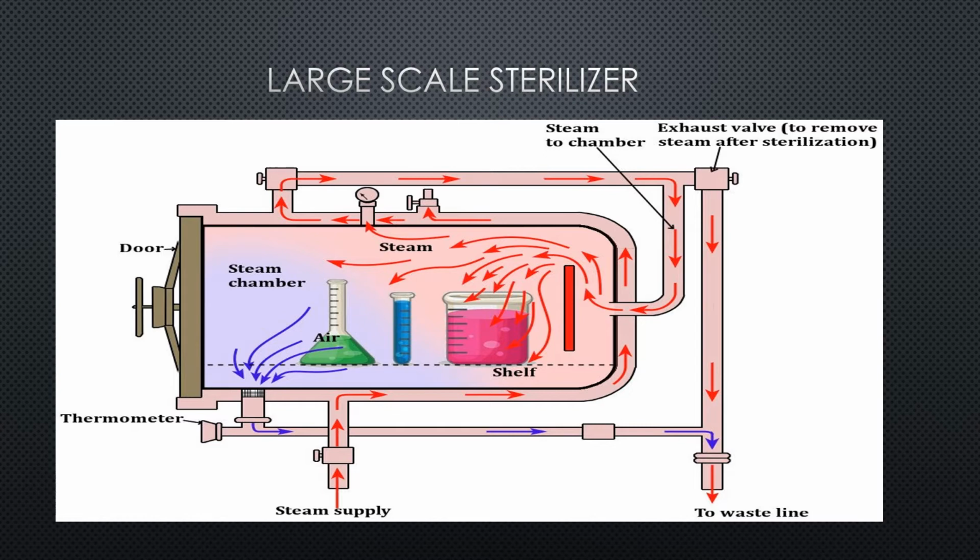During sterilization, the doors are held closed by a locking mechanism which prevents opening when the chamber is under pressure, and until the chamber has cooled to a preset temperature. Typically it is considered to be 80 degrees Celsius. The jacket can also be filled with water at the end of the cycle to facilitate cooling, and thus a reduction of the cycle time can be attained.